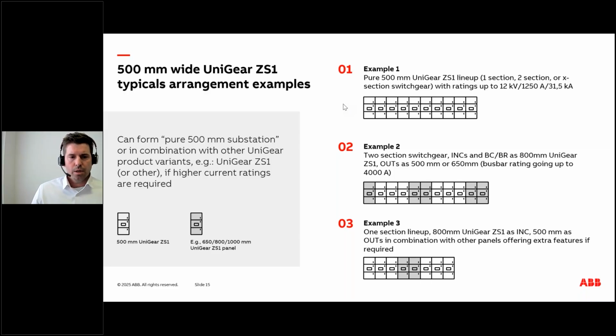These lineups can typically be used either in heavy industry or even data centers. The third lineup combines the 500mm from the Unigear ZS1 product line with other more powerful widths of this product line, where higher nominal current or higher busbar current is required. So in that case the 500mm can fit nicely into outgoing applications, while the incoming and busbar ratings go above 1250 amps.